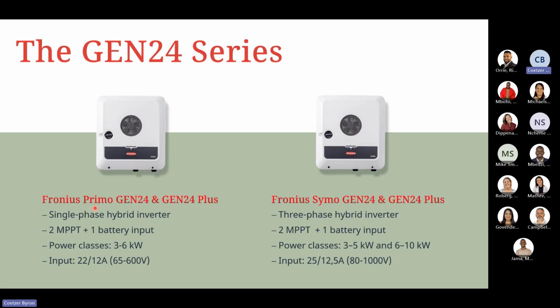So the Gen 24 is available as a Primo, so single phase, and also the Symo range. So again, three-phase units that can be used as either a grid tie unit or as a full hybrid inverter. So again, you've got a three-phase hybrid inverter, you've got 2 MPPT inputs, again, one single battery input on the DC side. And this is available in power classes 3 to 5 kilowatts. So for the smaller housings, which are exactly the same size as your normal single phase Gen 24. And then from 6 to 10, it's a larger housing that is holding the unit in place.